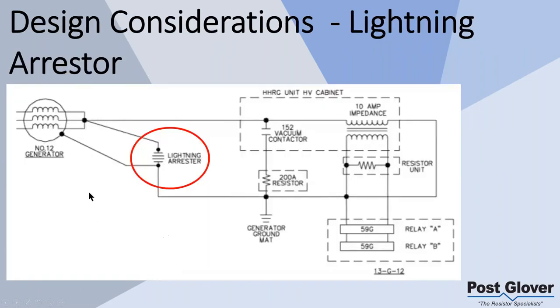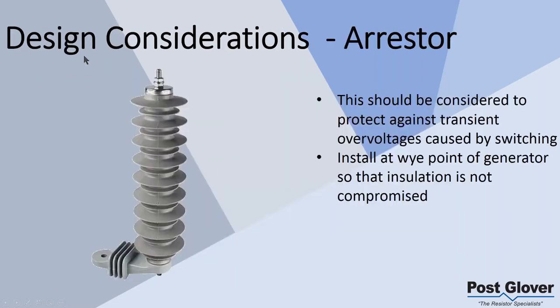So the second one is lightning arresters. It's kind of a domino effect of sorts, right? You need a fast speed switch. You're switching over from a higher current to a much lower current, and you're going to create transient voltages because of that. What you want to do is use a lightning arrestor or some surge suppression device essentially to control that, protecting the insulation of your generator. So because of this, we have to use this. It's an example of a medium voltage arrestor. It's just switching voltage essentially, but you want to install it at the Y point, just like that picture I just showed you indicated. You want to install it at the Y point so that the generator insulation is not compromised.